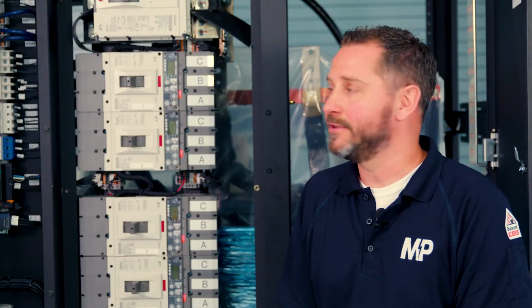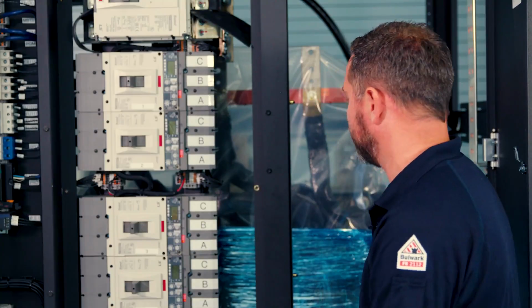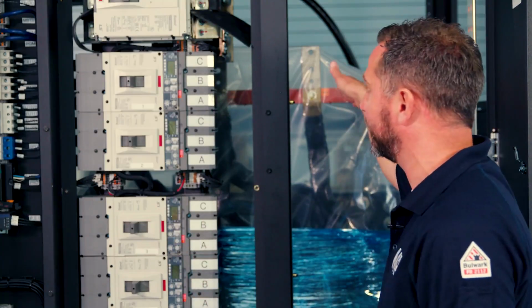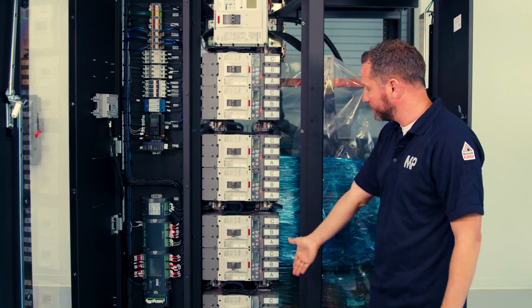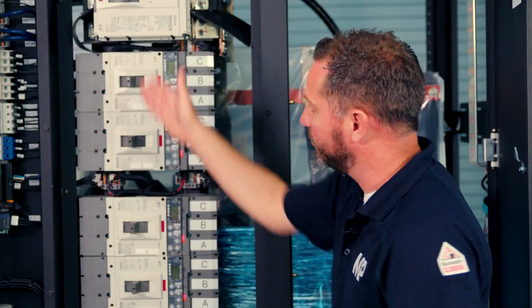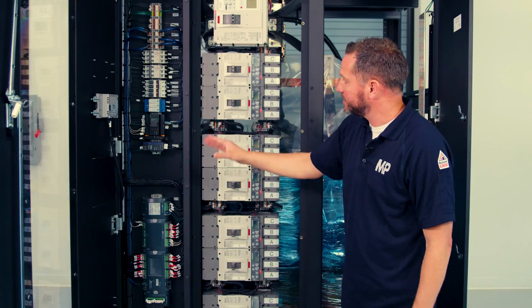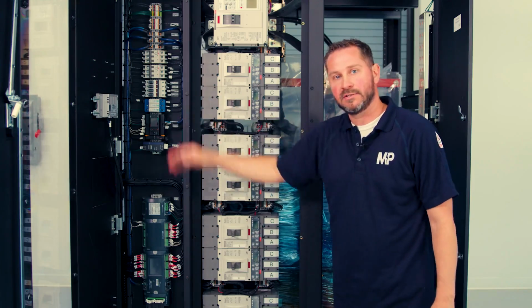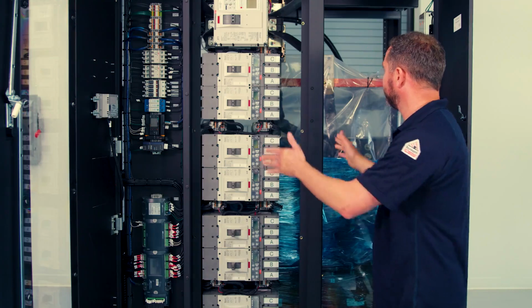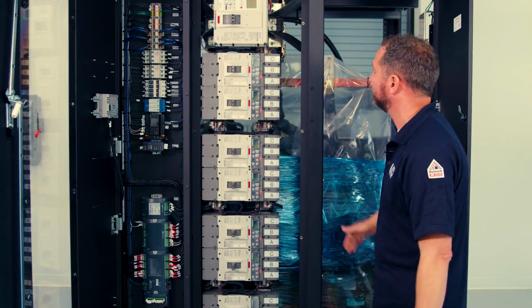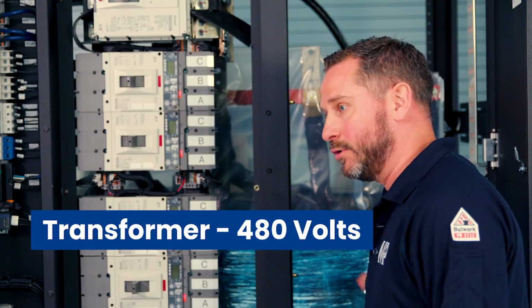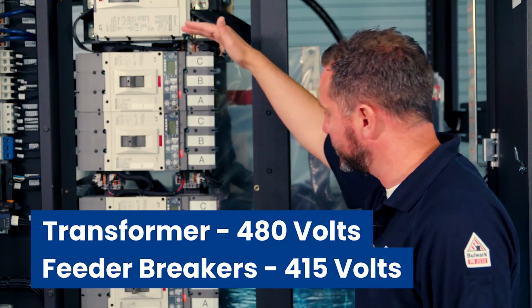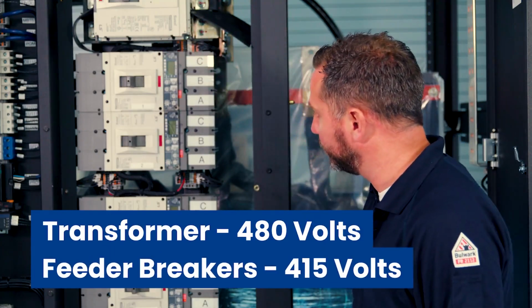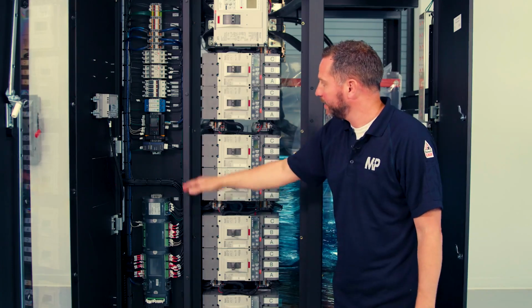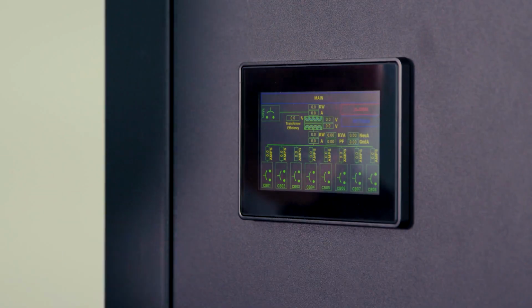Our main design of this PDU is a very nice compact unit. We have our transformer in the back, main breaker followed by all of our feeder breakers. This is a section separated from our control section, which is very nice and compact with all of our main three components. Operation of this PDU, a 500 kVA: basically we would shut this main breaker. 480 volt goes through the transformer. 415 on the other side is feeding all of our feeder breakers, which is monitored by all of our three main components. This is our HMI.